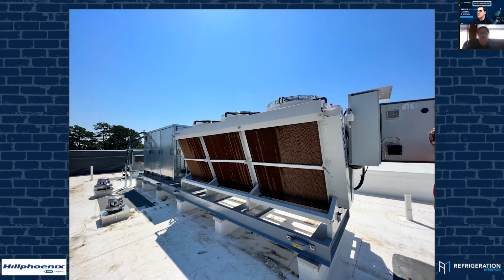What do you recommend cleaning them? What's the best way? Just hose and water? In the spring, prior to use. Before temperatures are going to start reaching 65 degrees, I would go out and do maintenance. And then the maintenance for them is taking them out and washing them with a hose and water, not a pressure washer for sure. Not a pressure wash, because this is cellulose. It'll bend real quick, and it will get brittle as it wets and dries out also. So you've got to be careful when you're washing out. Do a backwash on it and clean them out and put them back in.